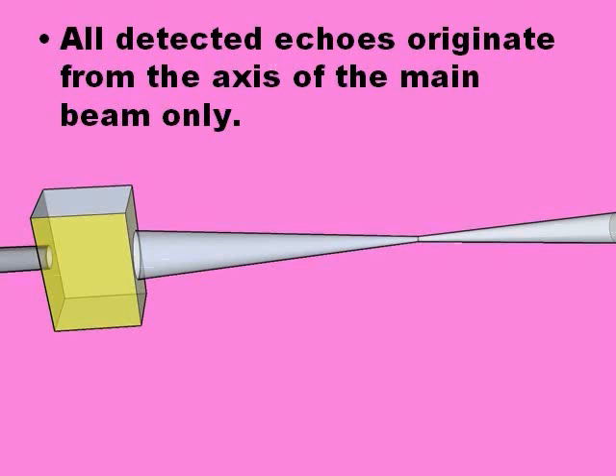A further assumption is that all echoes originate only from the axis of the beam. This is not always true, because sometimes the ultrasound transducer produces ultrasound outside the main beam, which also produces echoes.